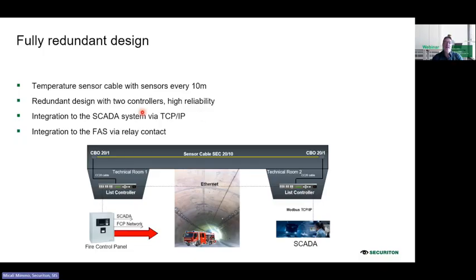This is when we have two controllers. One possibility is you have a tunnel, then you start with one controller here, and at the end of the tunnel, in the last technical room, you will have a second controller. In this case, you not only have redundancy where we have an interruption of the cable, but we will also have redundancy in case one of these two controllers fails. It can happen, but even then there will always be one controller taking control of all the sensors. So it's a fully redundant design.